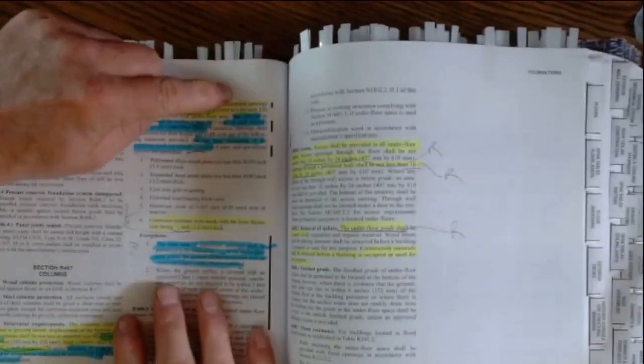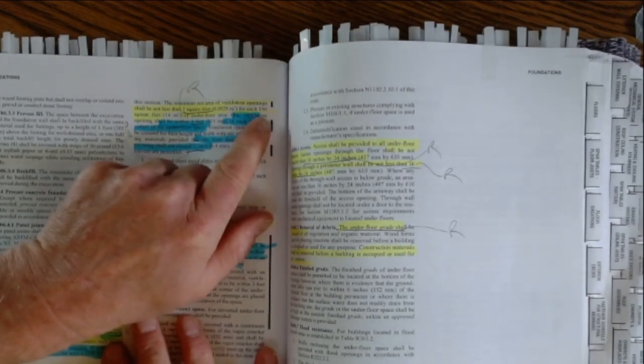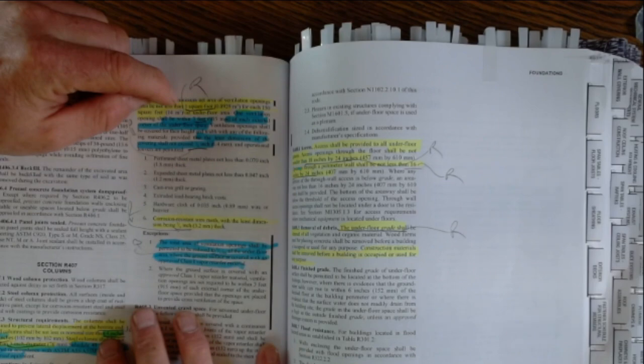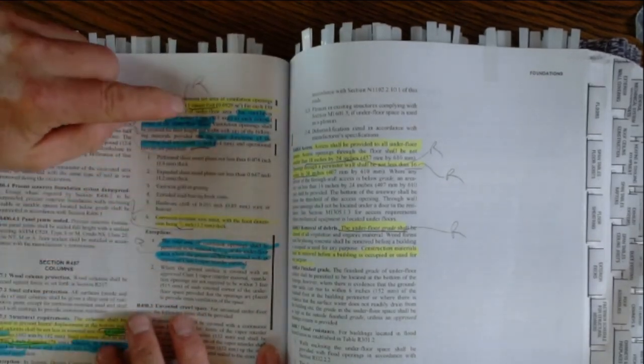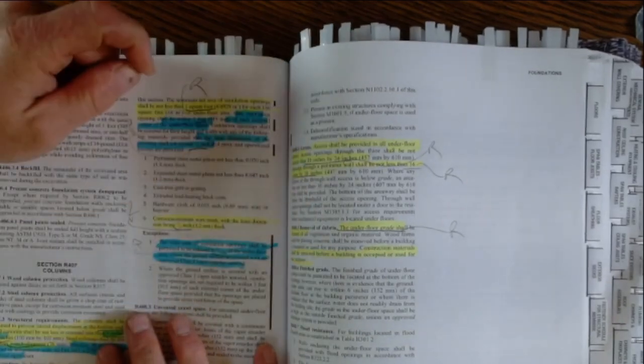Okay, this applies to attics and crawl spaces. There's ways to lower this or to raise this to 300 square feet, but if, for instance, you are in a standard, ground exposed crawl space, it's 1 square foot of required openings in your foundation for each 150 square feet.